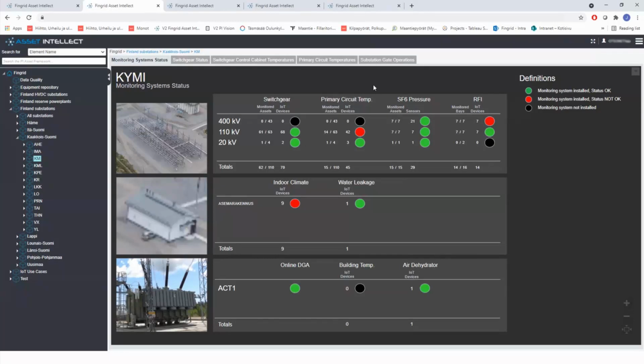In the primary circuit temperature monitoring, we have a red circle here, there's some sensor that doesn't work for some reason, we need to investigate that. The same situation is in the radio frequency interference measurements in the 400 kilovolt switchyard. I know there is some device with weak connectivity to the IoT gateway, so it doesn't send the data properly, causing this red color here.